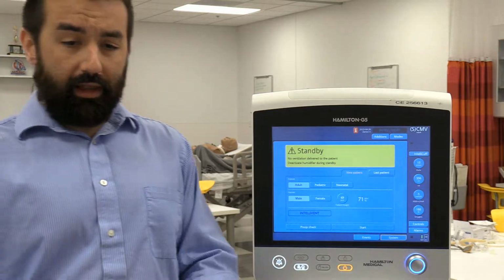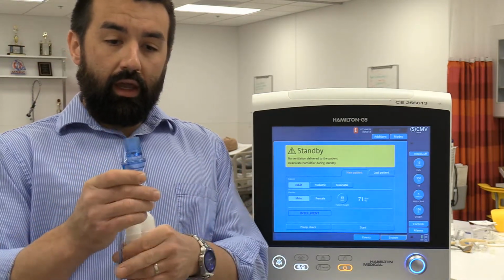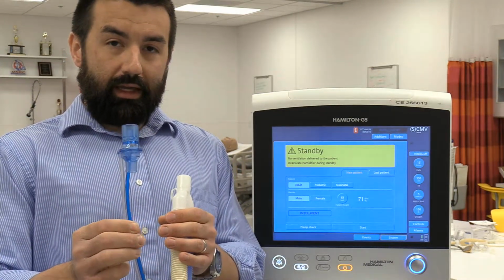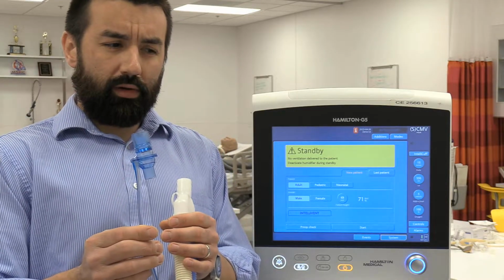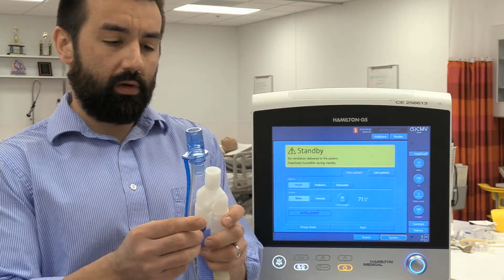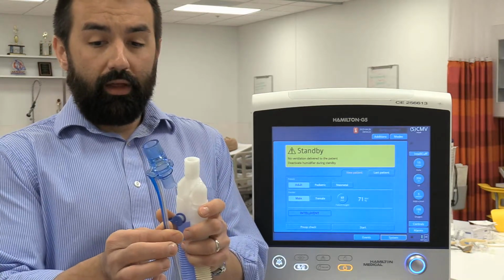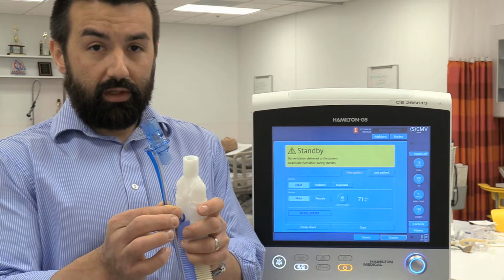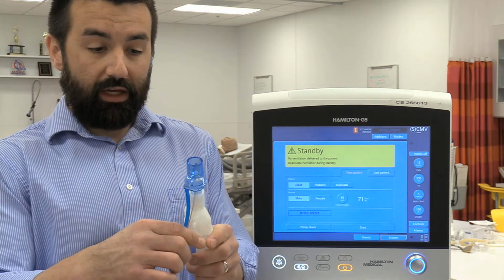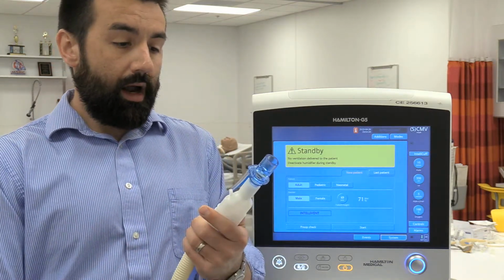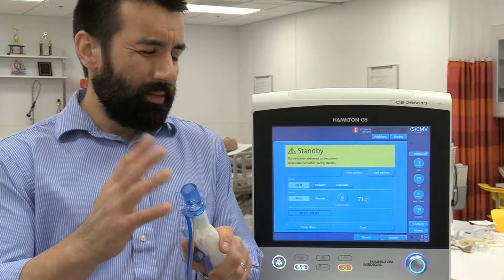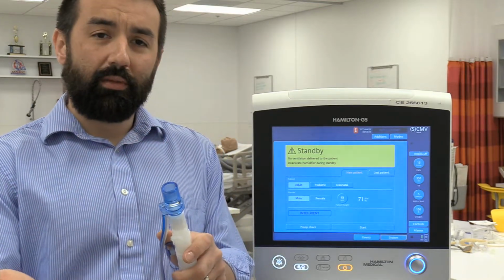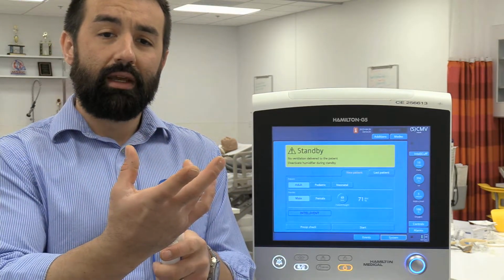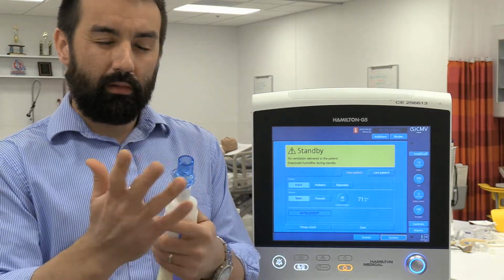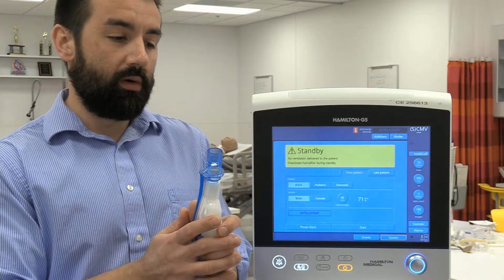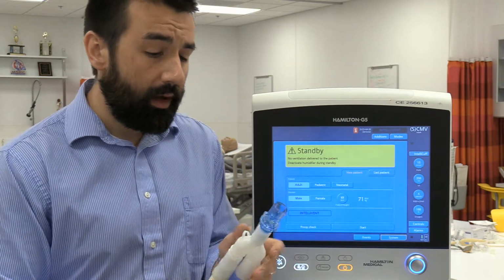So the first thing I'd like to point out on the Hamilton vents, in the adult world, is something really peculiar, okay? In the neo-peds world, or neo world, it's not uncommon. But Hamilton vents, even on adults, use a flow sensor that goes proximal to the patient and distal to the Y right here. So you generally want this as close to the patient, but if we're running passive humidity with an HME, I usually put the HME distal to this flow sensor. It provides a little bit extra protection against secretions and things like that building up.